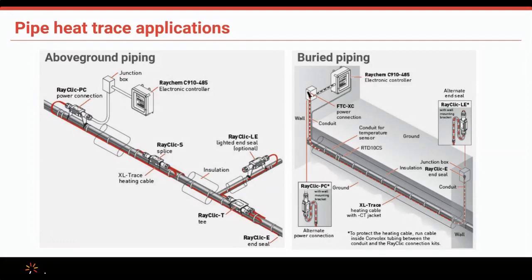The other thing I'll point out is that whenever you go below grade like this in a buried application, or for some specific product applications, like the greasy waste product, we do require the CT jacketing cable. We have a jacket cable that is water and non-organic rated. And then we have a product with a fluoropolymer jacket that's a little bit tougher. It's chemically resistant and corrosion resistant. So that's very important to think about when you have buried applications.